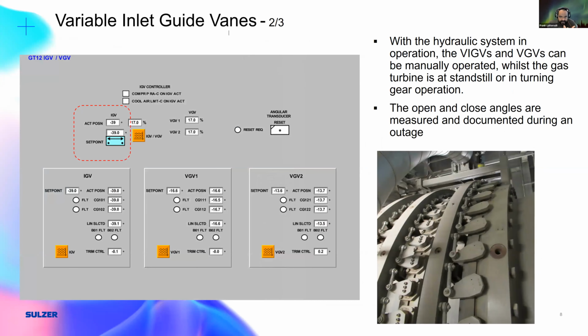This is the underlying, let's say, idea with this control layout. Now, to give you an idea what it looks like, this would be what you would see on your HMI, which is your human machine interface. In this case, it's a T3000 system. You could have TXP, you could have from ABB, the Elektro system. So you have an angle that you have to set. So typically when I go to site and there is an outage, the machine is opened up, the linkages are broken. And when I get to site and I'm about to start, I have to make sure that all the linkages are connected again. I have to take a protractor. I need to measure the angle, confirm whether the reading in the DCS matches the reading physically on the machine.